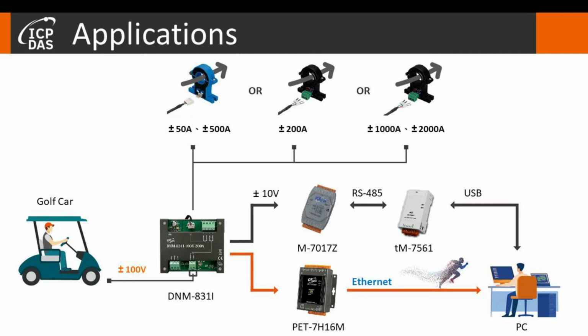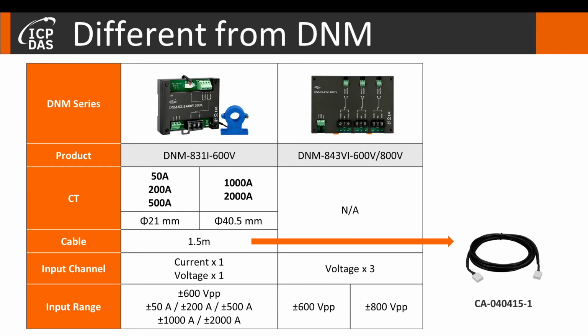Okay, but if you would like to operate faster, we also provide a way of the orange line to you. It's equipped with Ethernet and is used with PET7H16M, which connects with Ethernet to the PC and is easier on wiring work. The following is the difference between DNM-831I and the DNM-843VI. About the DNM-831I series, its maximum voltage input range is plus or minus 600 voltage, and the current input range is from plus or minus 50 amperes to plus or minus 2000 amperes.